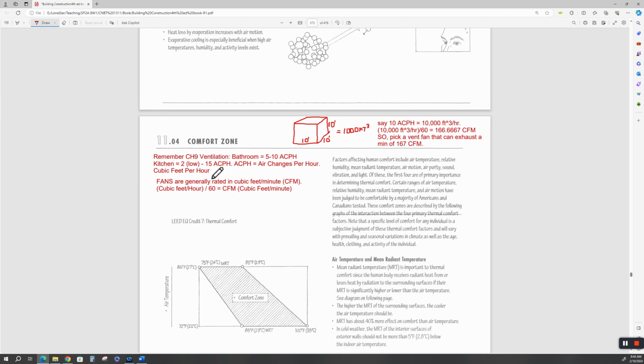For commercial kitchens, we're looking at 15 air changes per hour, and an ACPH is air changes per hour in cubic feet per hour. All right. Fans are generally rated in cubic feet per minute, CFM. And just go out to Home Depot or Lowe's and look at their exhaust fans for bathrooms and kitchens and stuff like that. And you'll see that, you know, they're sized. So you take cubic feet per hour and you divide that by 60 because it's 60 minutes in an hour, right? And you get cubic feet per minute.